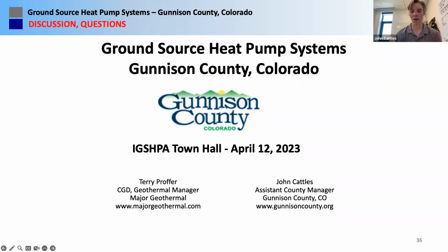The lowest temperature I've seen on a building: we had a power outage, and when the power came back on, there was a weird brownout condition. It actually didn't fault any of our heat pumps, but our loop pumps didn't come back online, and I didn't have an alarm set up to know that. So the building ran for about 36 hours without the ground loop. When we realized that and our heat pumps started shutting down at their low limit, we reset the pumps and were able to get the ground loop going. I saw that ground loop drop to about 32 degrees for about an hour, and then it recovered by midday. That was the coldest I've ever seen.